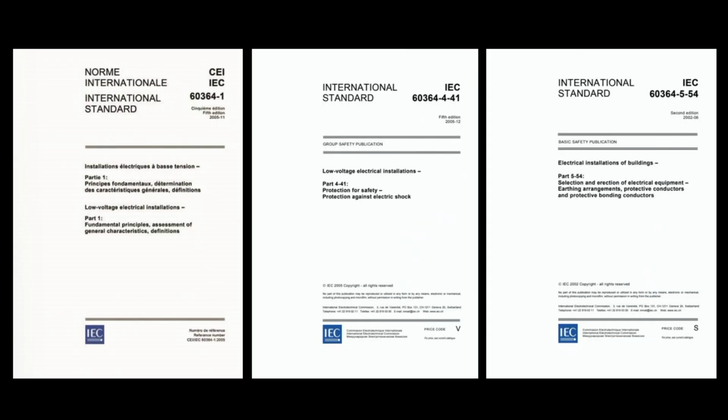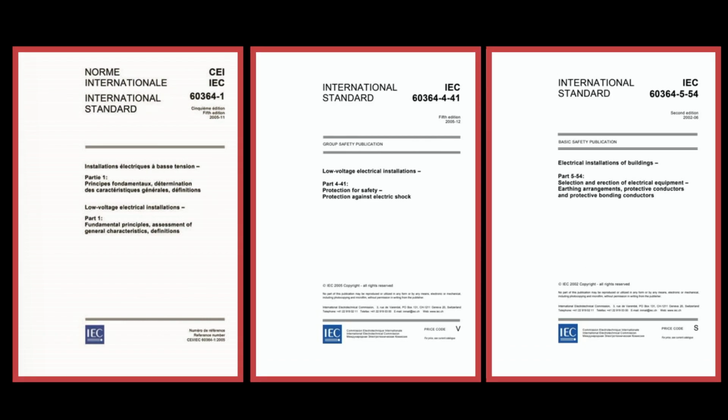Looking at the international scene, we have the equivalent of the NEC and the Canadian Electrical Code, and this document is IEC 60364. And if you notice here on the screen, there's a different approach. So in North America, we have one book that has all the requirements, the Canadian Code or the National Electrical Code in the US. In Europe or internationally, the IEC, they have different parts and different sections that are addressing installation requirements as well, but not as one full document.